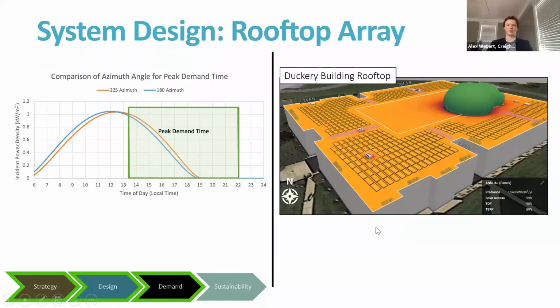As we assess the Duckery Building rooftop for PV integration, a priority was to maximize offset of load consumption. We decided an elevation tilt angle of 10 degrees will maximize power density for the building while minimizing potential hazards from wind. While modules oriented at an azimuth of 180 degrees have the greatest annual production, the figure on the left shows that by assuming an azimuth of 225 degrees southwest, our modules will deeper penetrate load consumption into peak demand time with minimal annual losses.